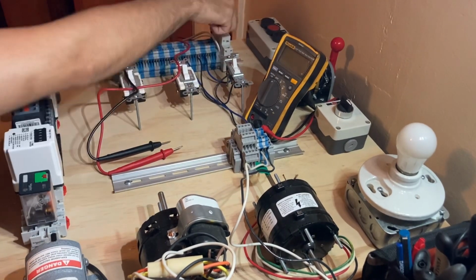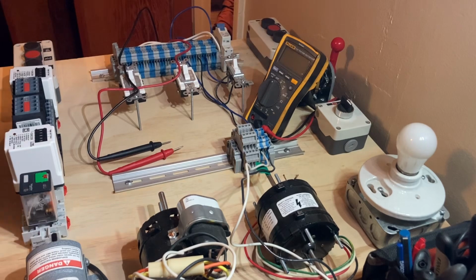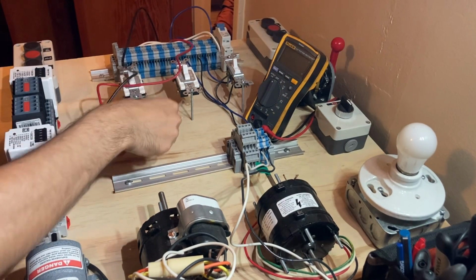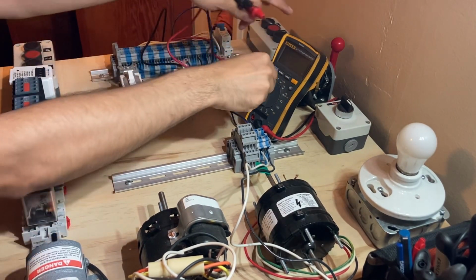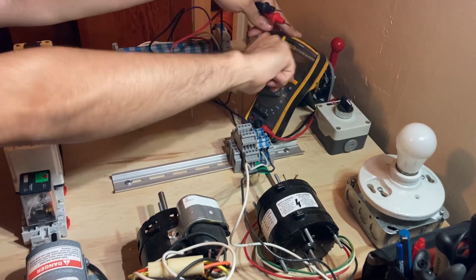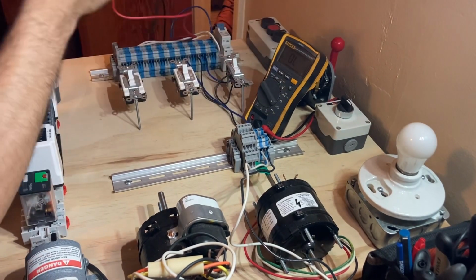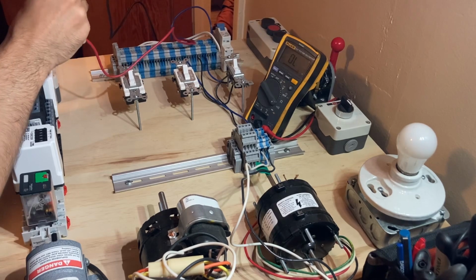Now we're going to run the same tests, but with voltage. So that was with the power off. That's the safest way to test your circuit, that everything's connected properly. But if we want to test with voltage on, we switch our meter to volts, alternating current. First, I'm going to test my leads here.